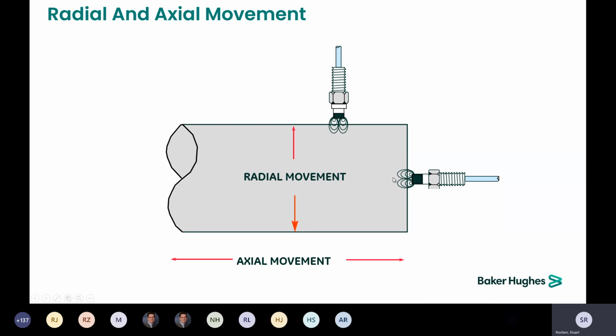We also measure axial movement, looking at thrust, differential expansion, rotor expansion, and case expansion. Case expansion is not a very common use for proximity probes. Usually it's a greater distance than the proximity probes can properly read, so often that's used with an LVDT.